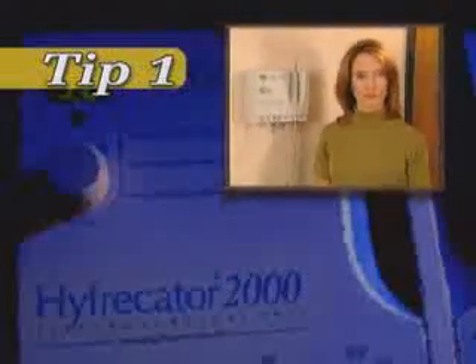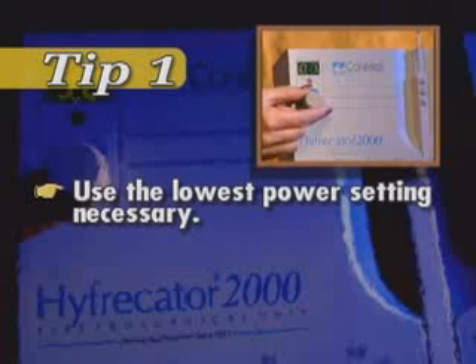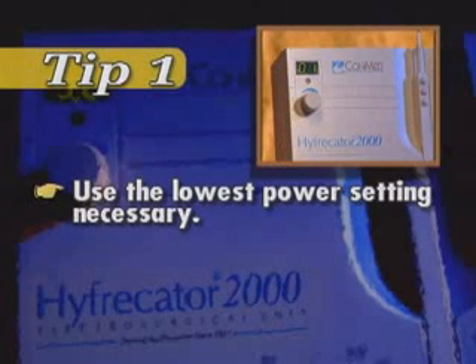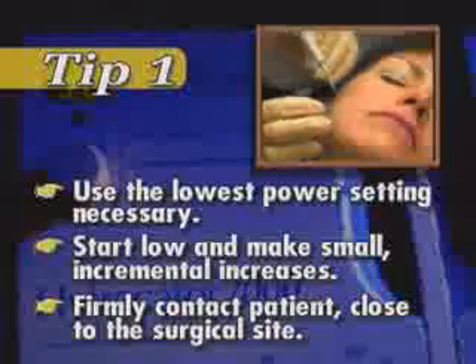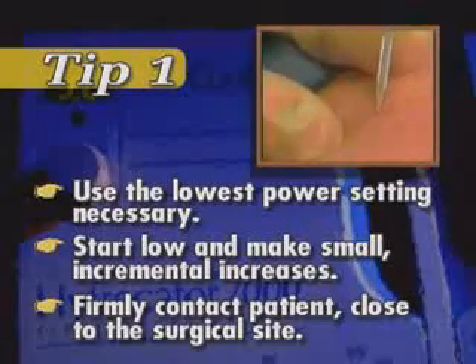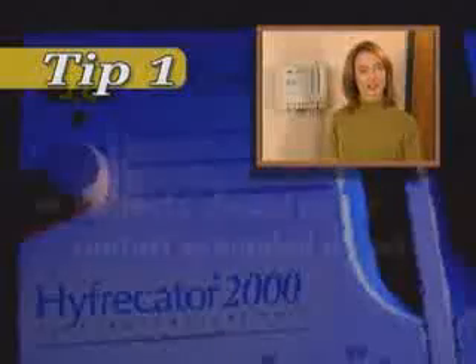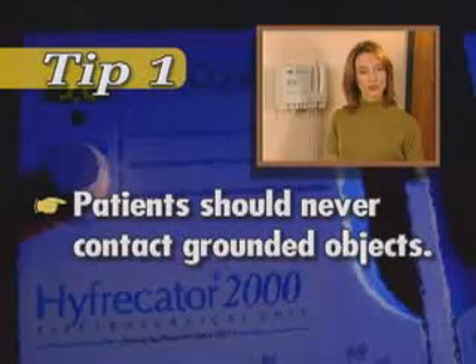Here are some tips to help you perform procedures with the Conmed Hyfrecator 2000. Tip one: the rule of thumb with any electrosurgical device is to use the lowest power setting necessary to achieve the desired clinical effect and to provide an effective pathway for the energy to complete its circuit to ground. Start at a low power setting and incrementally adjust until you achieve the desired clinical effect. Be sure to make firm contact with the patient as close to the surgical site as possible for optimal coupling and maximum coagulation efficiency. Remember that patients should never contact grounded objects, such as metal rails, when current is being applied during electrosurgical procedures.